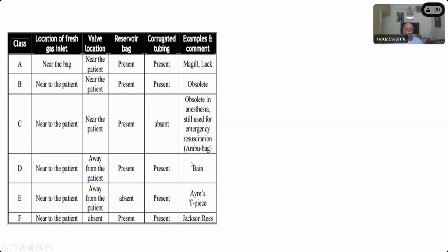Through an outer transparent corrugated tube, you can see the inner green tube, which is the fresh gas delivery tube. So visual inspection itself will be able to tell you most of the time whether there is any breakage or not. Whereas in the Lack circuit, you can't do that, because the inner tube is the expiratory tube and the outer tube is the delivery tube or inspiratory limb. So this is an important difference that you have to know.